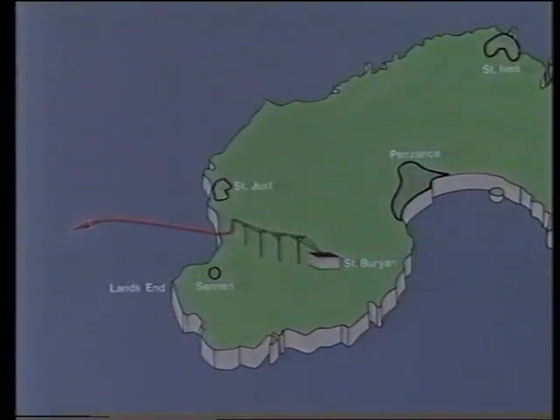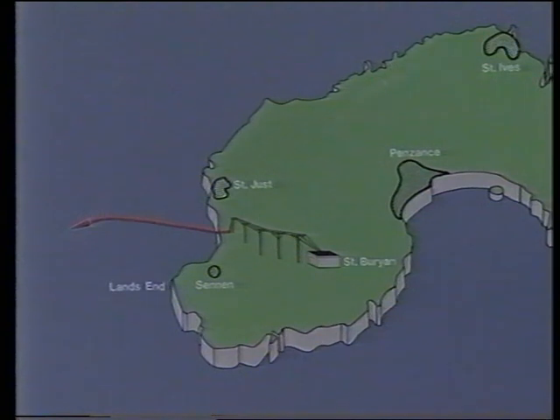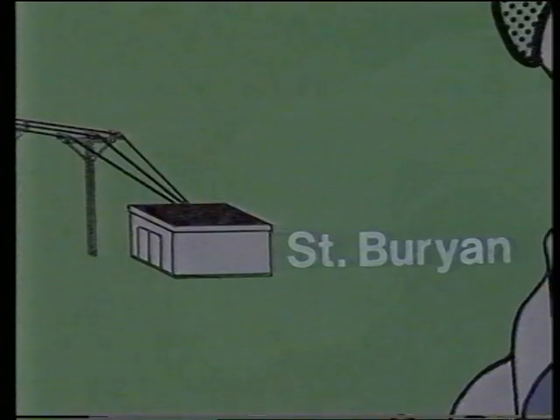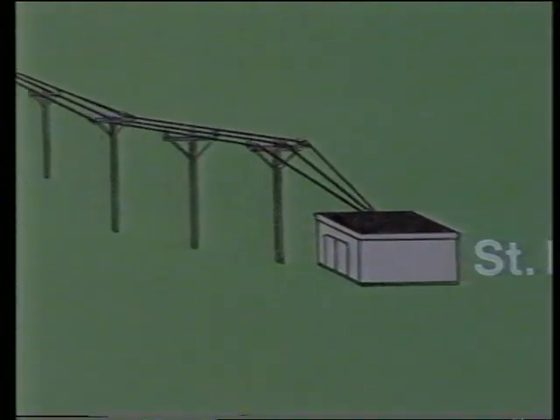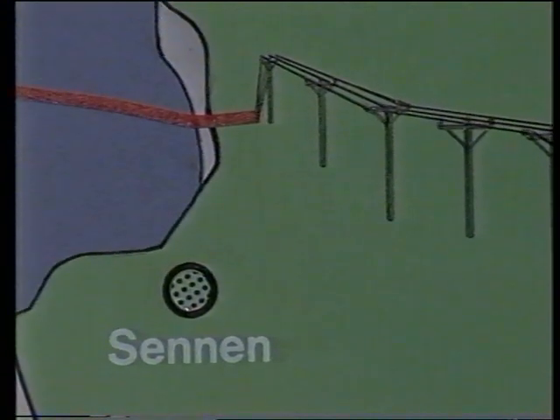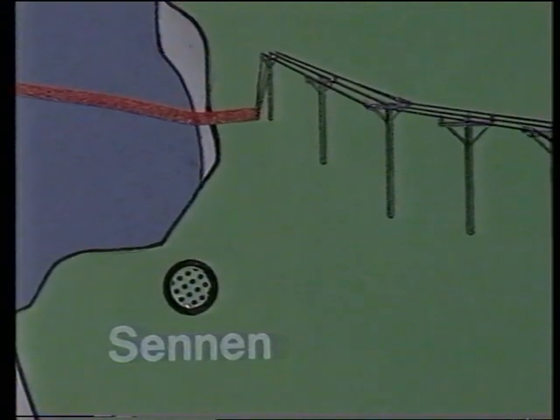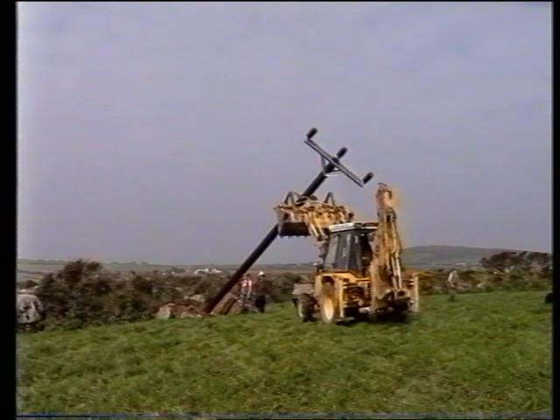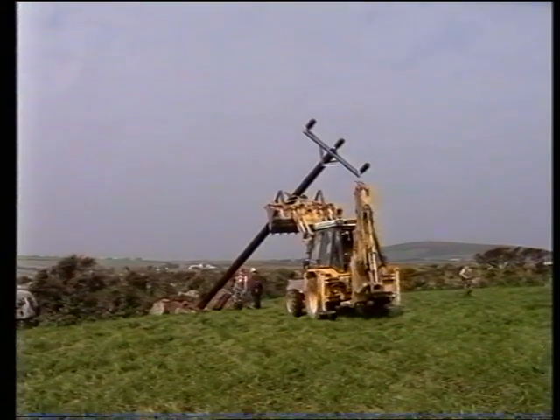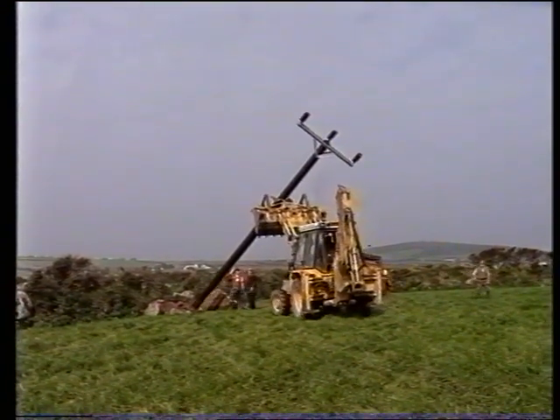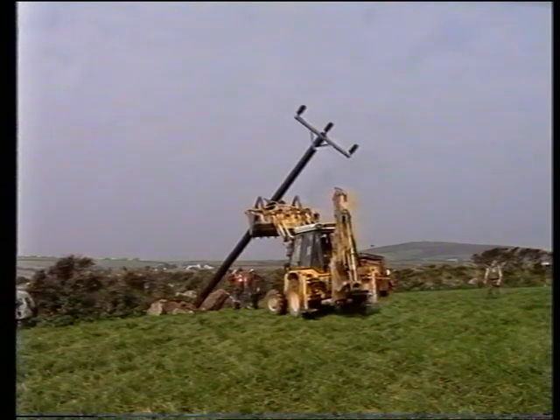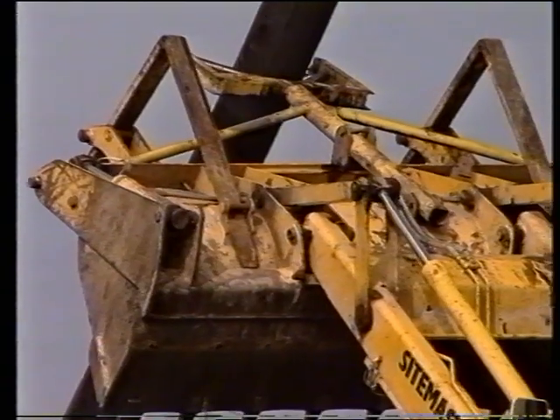Far to the west, down in Cornwall, SWEB is constructing an entirely new power line ready to link St Buryan substation with the submarine cable coming into the bay near Sennen. A mechanical digger pushes each pole up in turn, fitting it snugly into a 6-foot hole specially shaped to give greater stability.